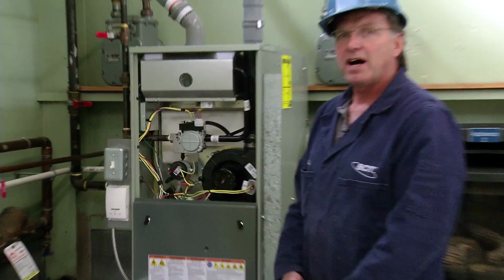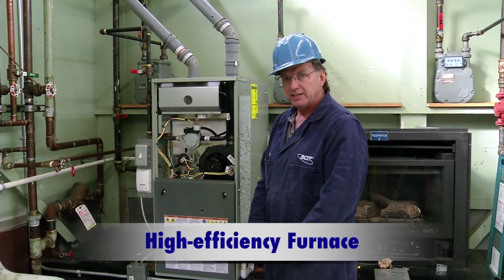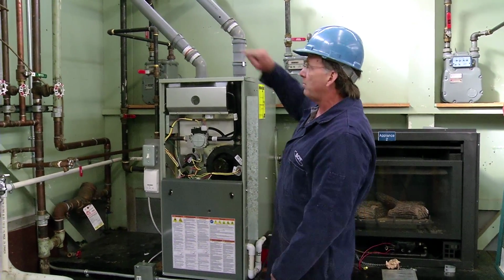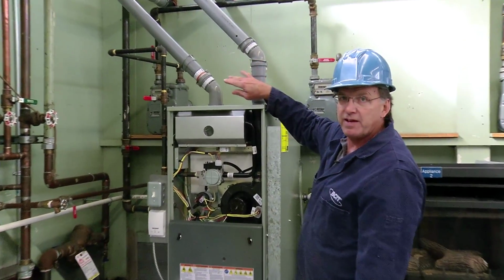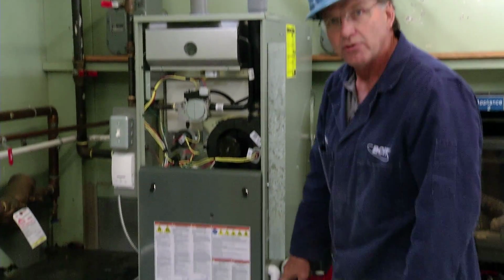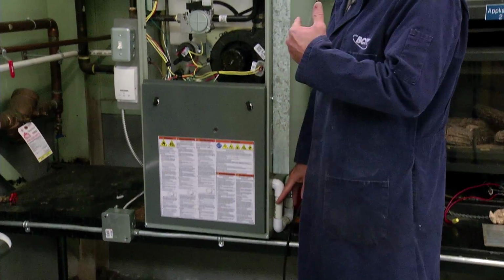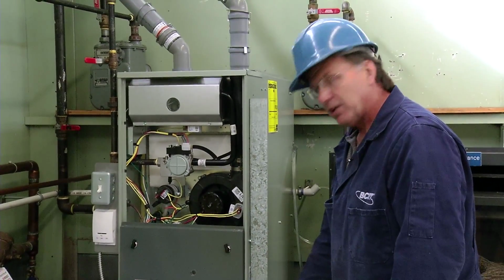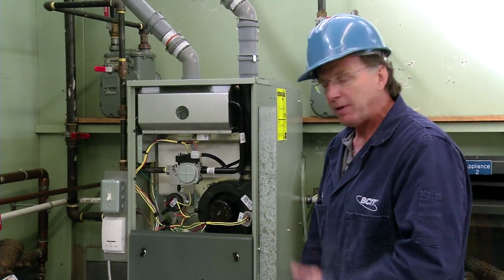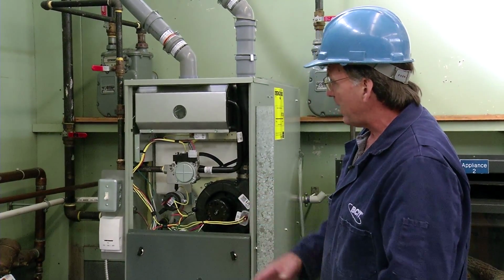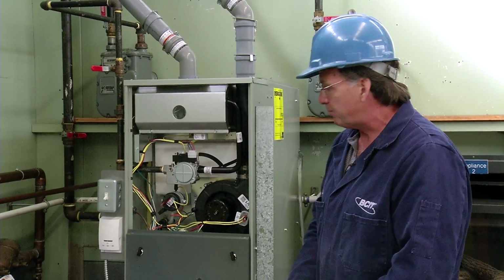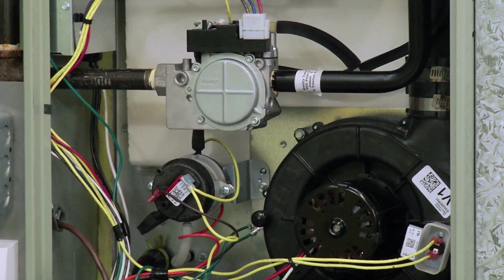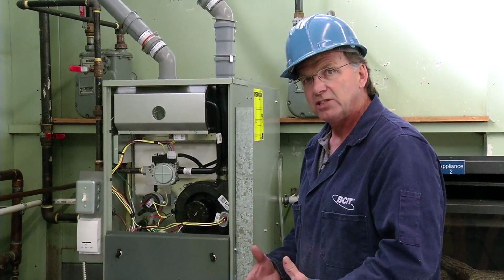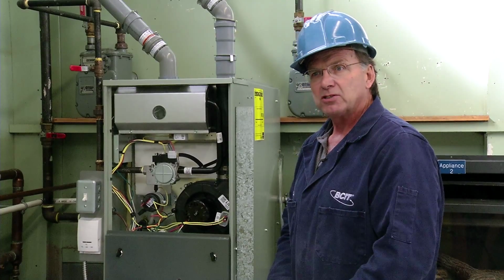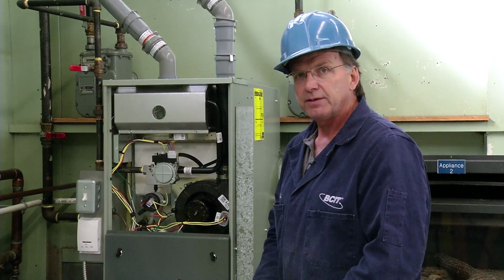Here we have an example of a high efficiency furnace. This is a condensing combustion system. You can tell by the fact that it has plastic pipes for vents, and it has a condensate drain. So all the flue gases are going to be condensed, and we're going to recover the latent heat and put it back into our air. In this case here, we have a two-stage. It's not variable input. It is just a simple two-stage system, and if the first stage isn't firing well enough, then we can add more heat by opening up yet another source of gas and going to a second input.